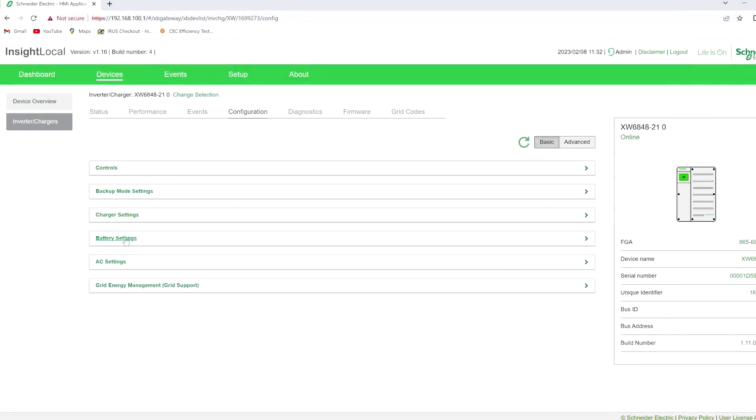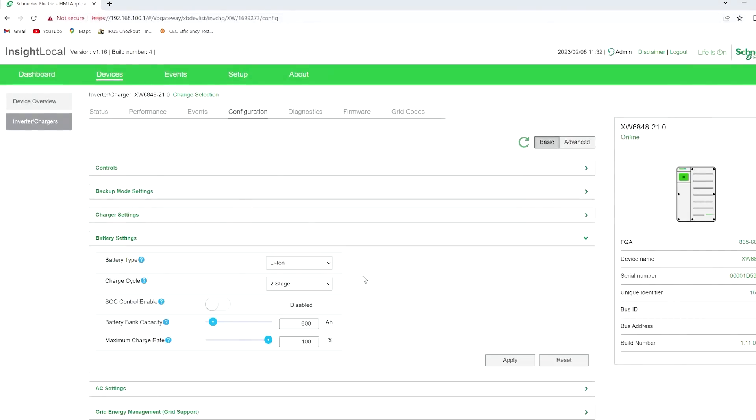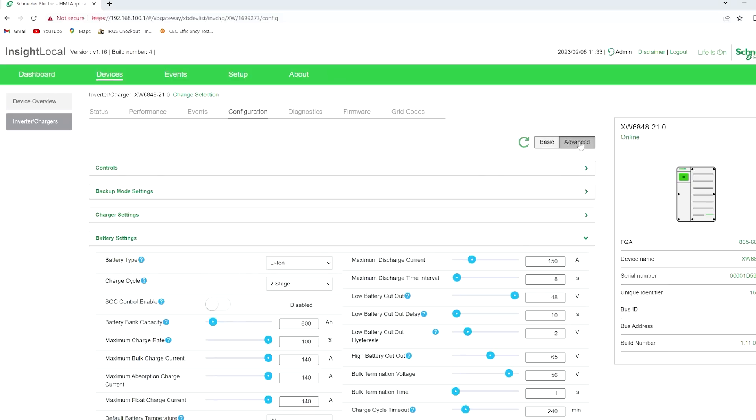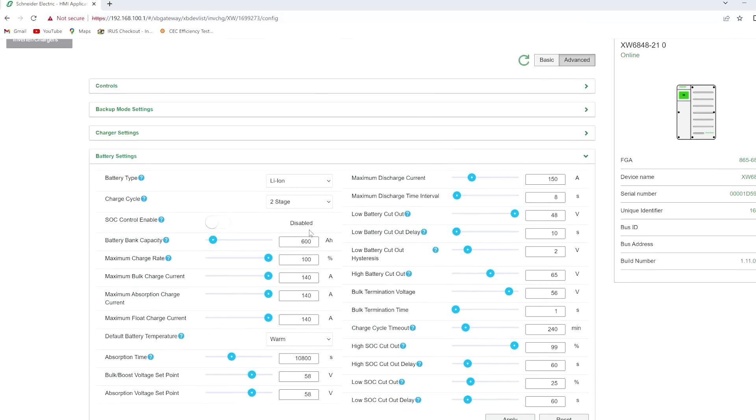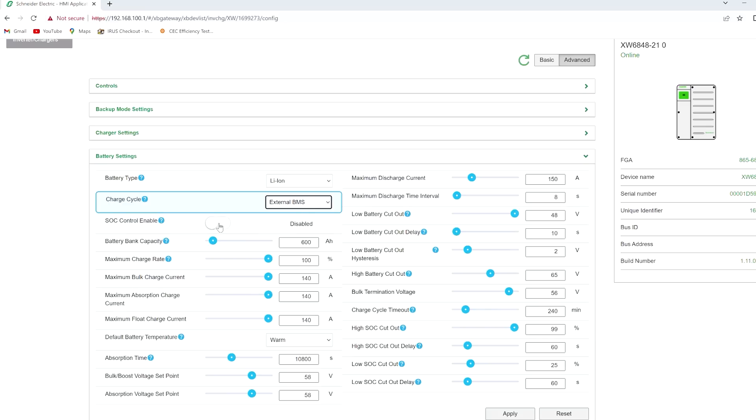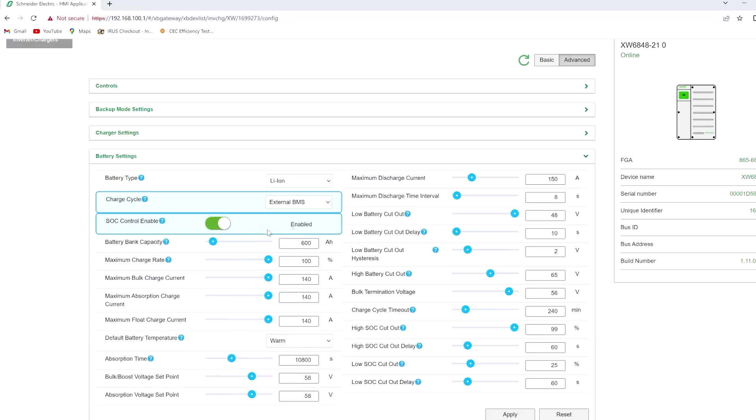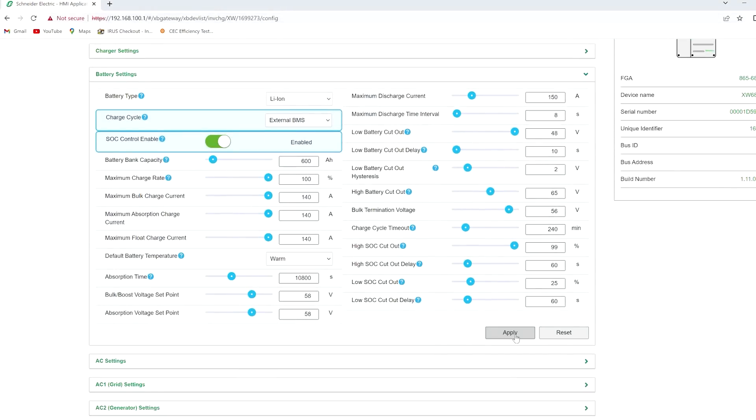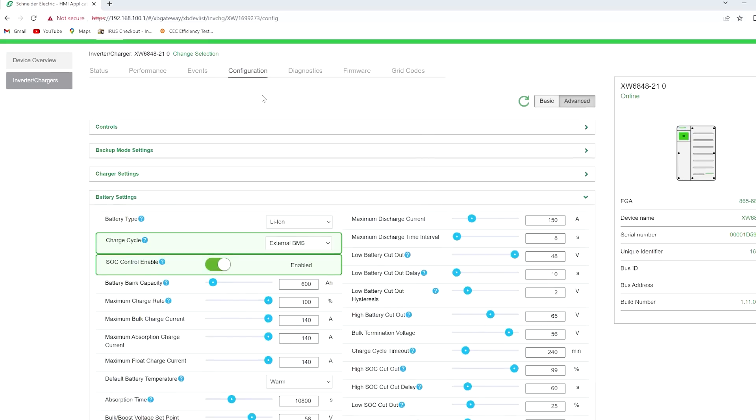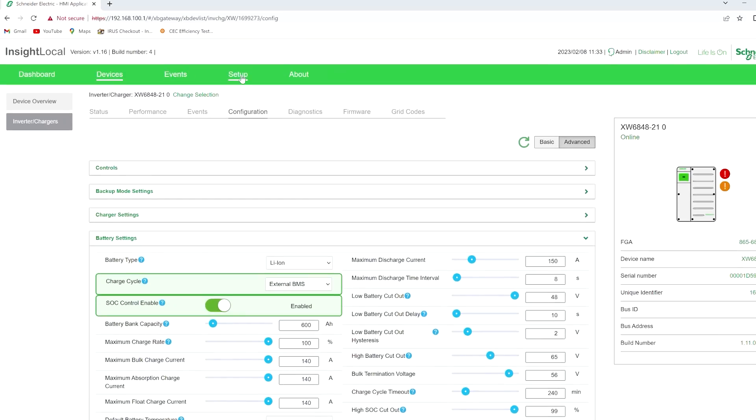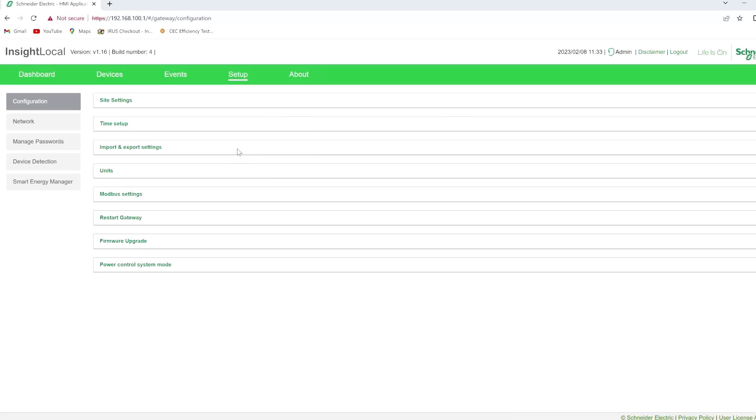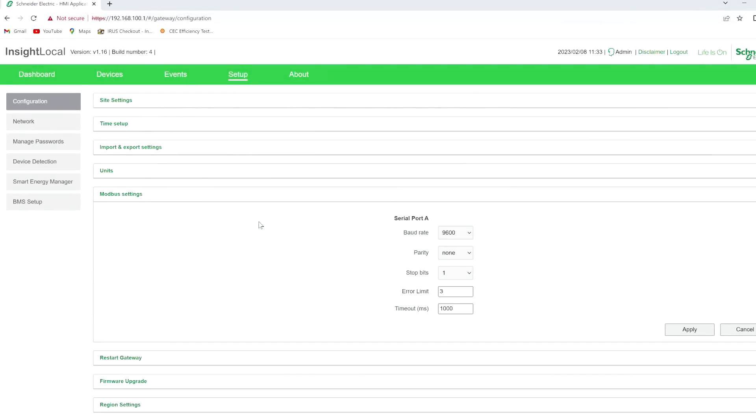We'll hit configuration. Now we need to set up the battery settings, but we don't have the ability to set up. I don't know if you can see this, but there's a drop down list and it says lithium ion, but it doesn't allow for the external BMS. So we'll click the advanced setting, and then over here we can click external BMS, and we'll enable the state of charge control. Hit apply.